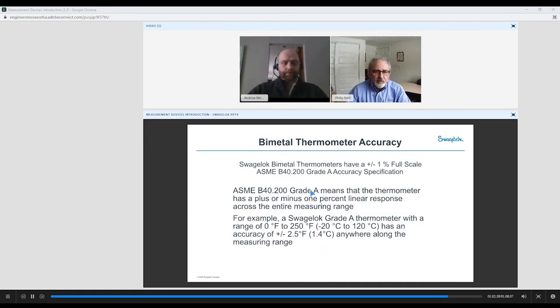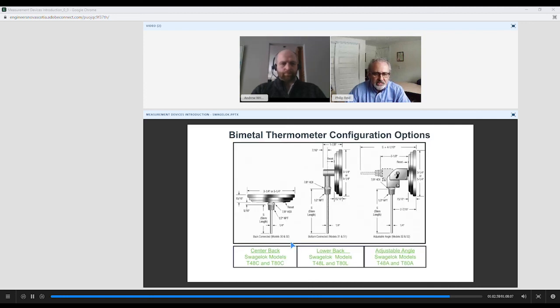So ASME B40.200, grade A means that the thermometer has a plus or minus of 1%, and just using a simple bit of math, 0 to 250 degrees Fahrenheit, the accuracy will be plus or minus 2.5 degrees Fahrenheit, or -20 to 120 C, 1.4 C, anywhere along that measuring scale. So it's not just in that middle third.